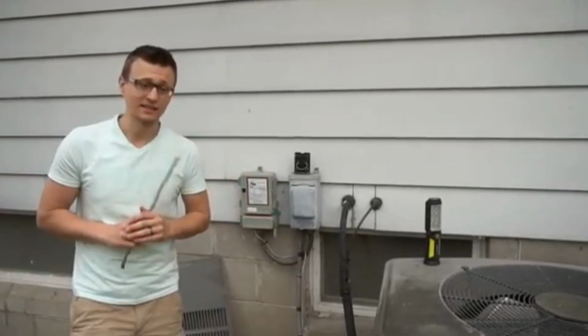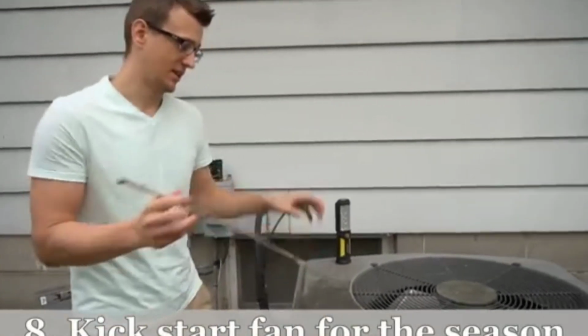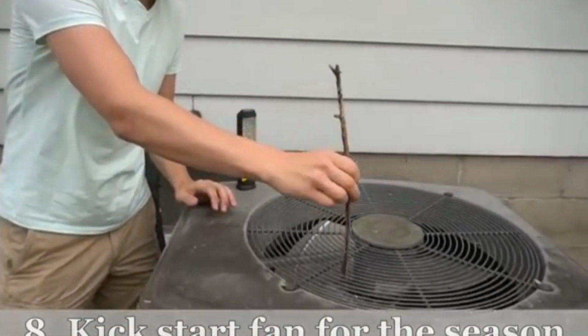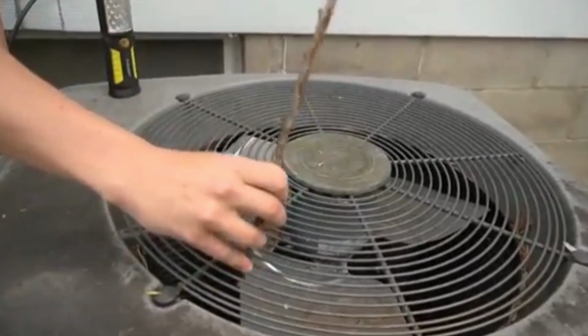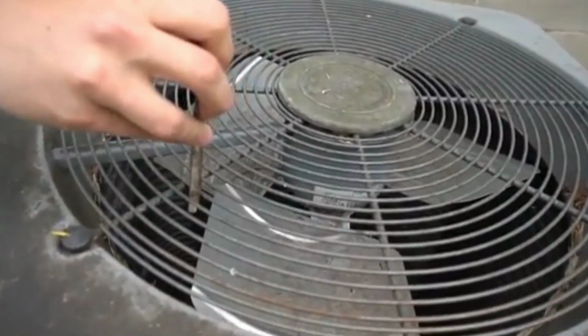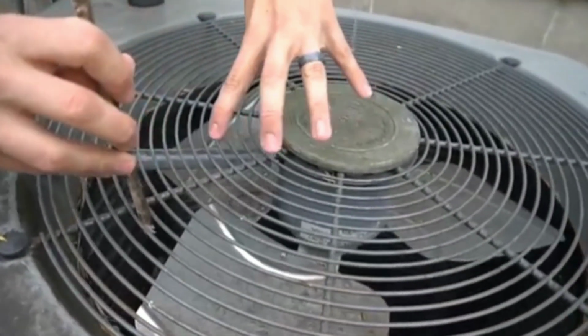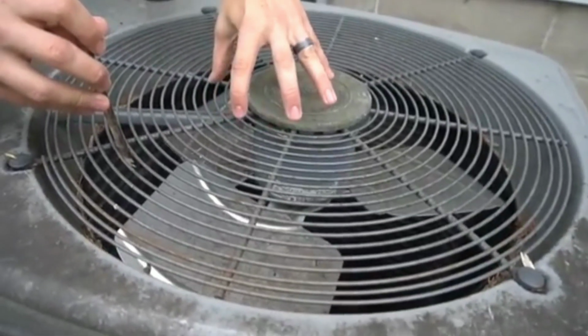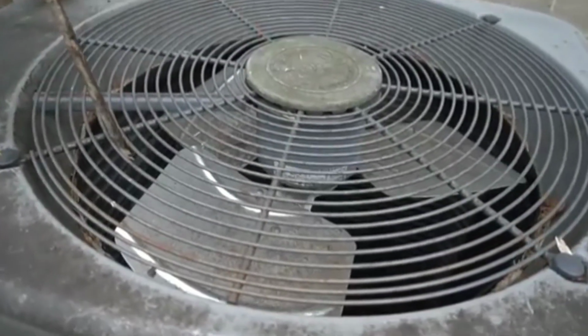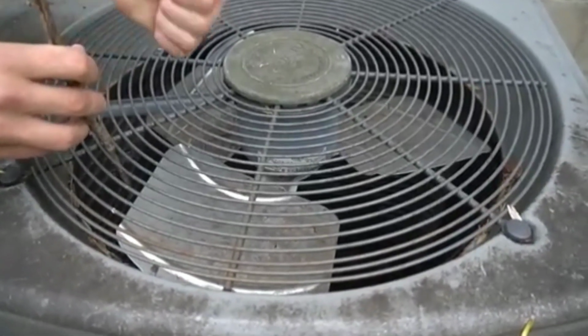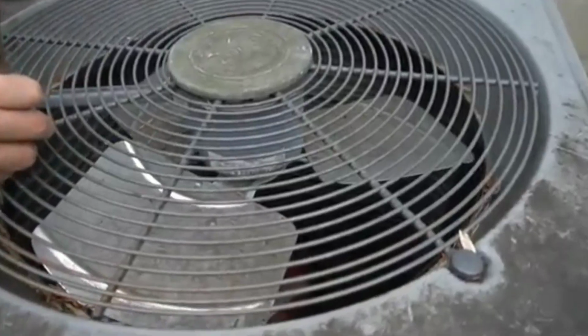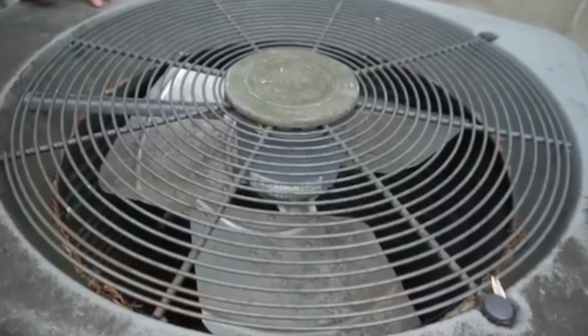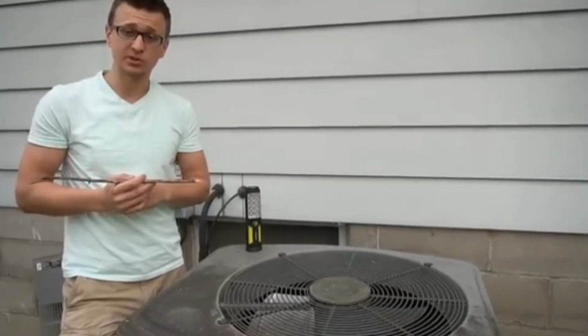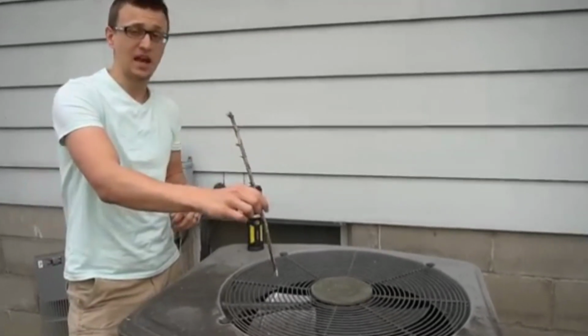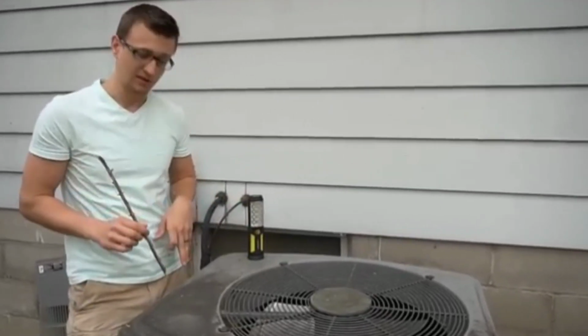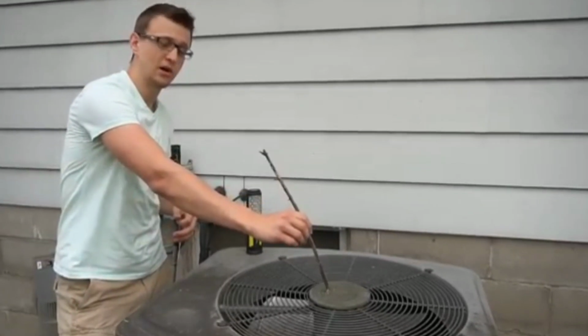And maintenance tip number 8 is that over the winter, sometimes as the unit sat there the whole winter, the fan will kind of seize up just a little bit. And a lot of times there will be nothing wrong with the fan. So the first time, when it turns on, the compressor will turn on, but the fan either will spin really slowly, barely moving at all, or it will just sit there and hum and do nothing. A lot of times, just putting a stick in here or taking a screwdriver and just helping that little fan out, give it a kick start, is all that is needed to get that fan going. And after that initial time, the fan will start with no problems. If that keeps happening to you though, then you do have a problem. Either the capacitor's weak or dead, or there's something wrong with the motor.